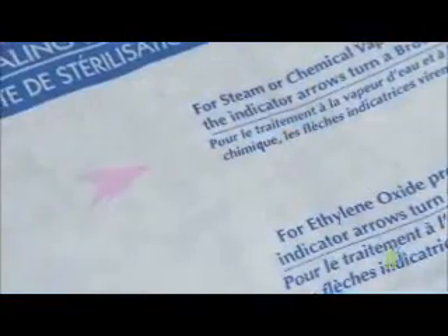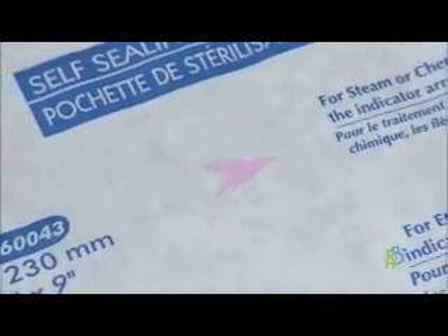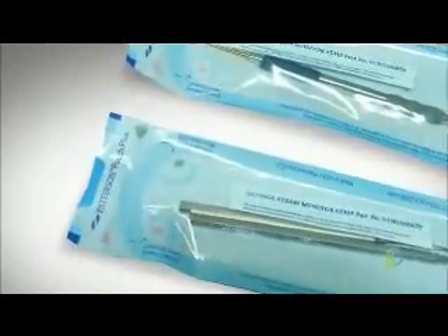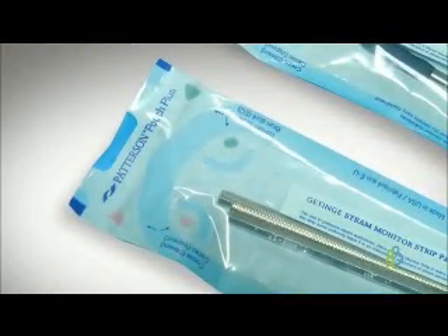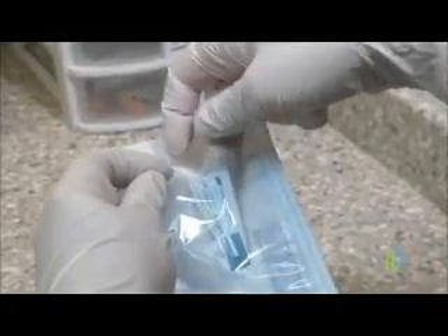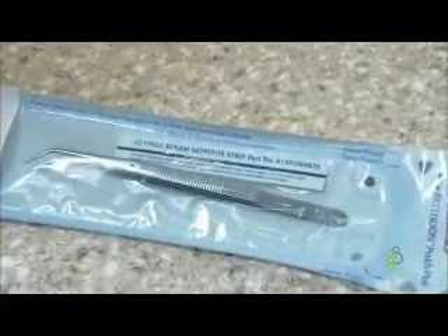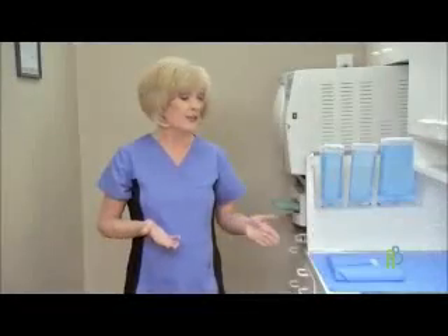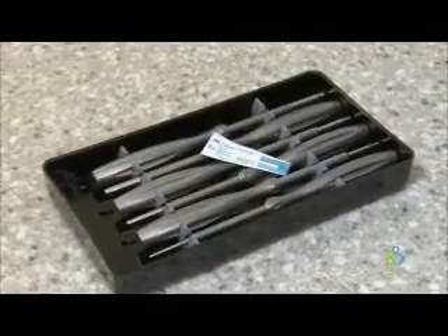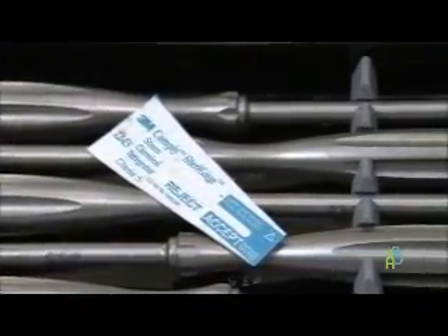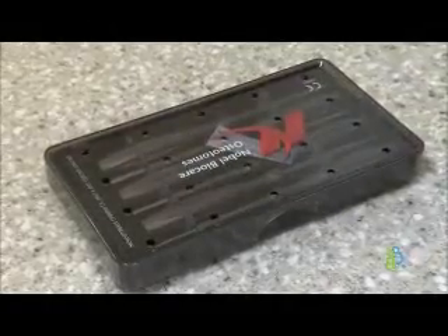All packages must have a Class 1 chemical process indicator on the outside of the package. Process indicators are used to allow a visual check that the package has been through the sterilization process, but do not provide any assurance of the success of the sterilization process. All packages must have a Class 4 or 5 internal chemical indicator. The indicator must be placed inside the package in an area considered the most difficult for the steam to penetrate. If the package of devices is intended to be used in conjunction with implantable devices, a Class 5 indicator must be used. Chemical indicators do not test for sterility. They provide information on whether or not the conditions to achieve sterility have been met within the package.